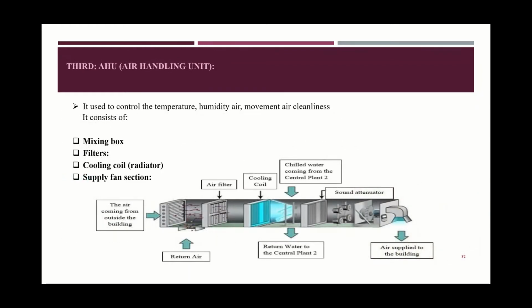The third element that I want to discuss with you is the air handling unit, or AHU. Air handling unit is a device used to regulate and circulate air as part of a heating, ventilation, and air conditioning system. It's used to control the temperature, humidity, air movement, and air cleanliness. It consists of a mixing box. This box has an air inlet that is attached to the damper. This is the place where the outside air and the return air are mixed to provide the correct proportion of air to be distributed to the space that is to be conditioned.